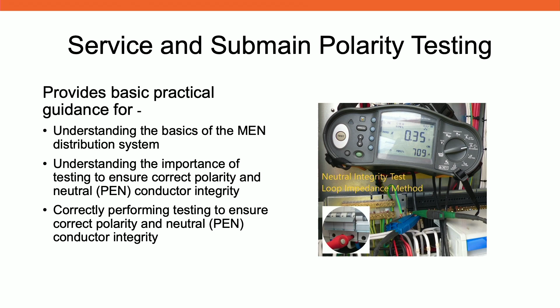Once you understand that, you know the importance of getting the polarity testing correct, so that active is active, neutral is neutral, earth is earth, and then that the neutral conductor is continuous back to the star point of the transformer. That's very, very critical. So this book gives you guidance on various methods of testing that for service and submains.